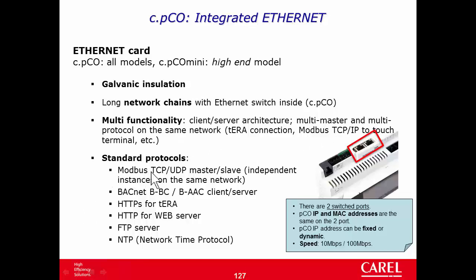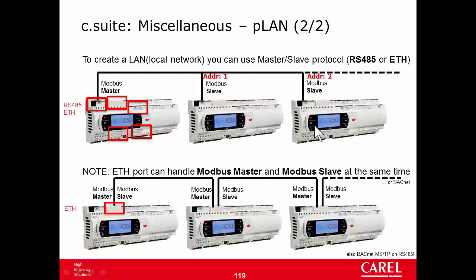Supported protocols include Modbus TCP or UDP master, Modbus TCP or UDP slave, BACnet client and BACnet server, HTTP for Tera, the web server, FTP, and NTP. Since Modbus master and slave can run simultaneously, multi-master networks are possible, as in a previous exercise. The same applies to BACnet as a client-server protocol.